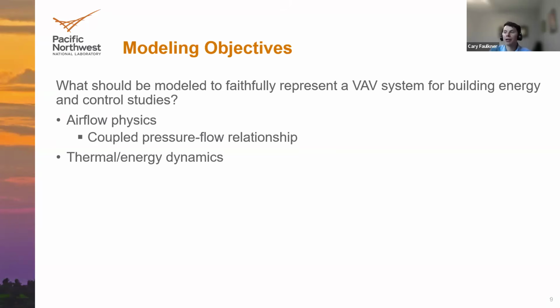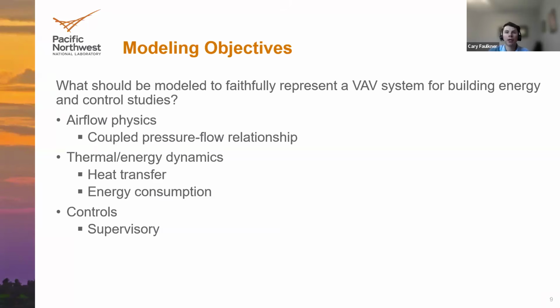Then obviously we need the thermal and energy dynamics. This includes the heat transfer from the coils or from the zones, and then coming back to the air handling unit from the return ducts, and then the energy consumption to model the energy usage of the coils or the fan, things like that. And then the last key aspect, since those are more the fundamental physics of VAV systems, is the control aspect, which obviously connects to the physics, but is about how these systems are controlled. This includes the supervisory controls, which is more what's happening at the set point level at the air handling unit, for example, or at the zone set points.